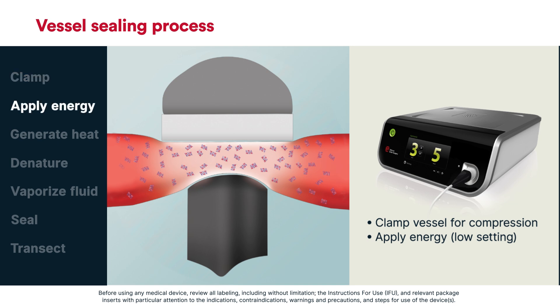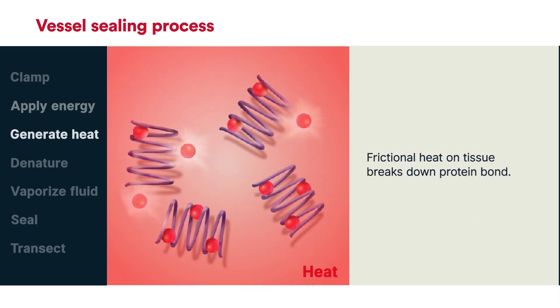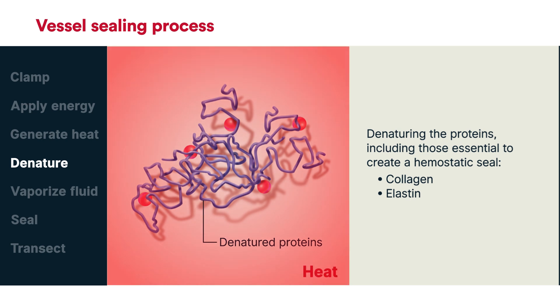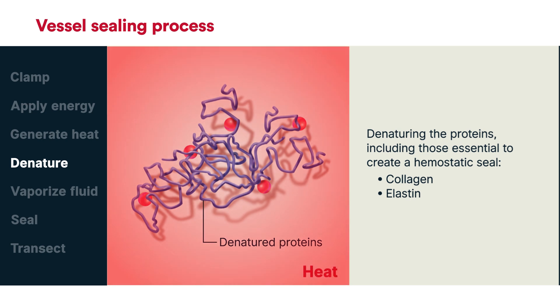It begins with clamping on the vessel to achieve compression. The surgeon applies energy at a low power setting, which maximizes coagulation. Frictional heat on tissue breaks down protein-hydrogen bonds, denaturing proteins, including those essential to create a hemostatic seal, such as collagen and elastin.